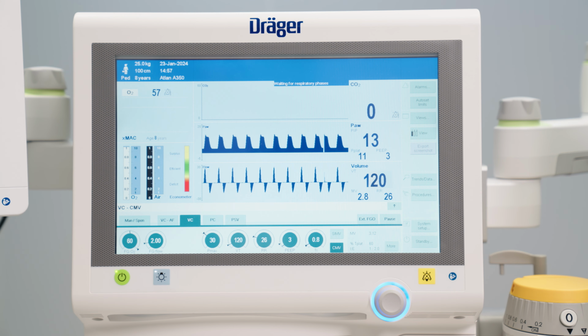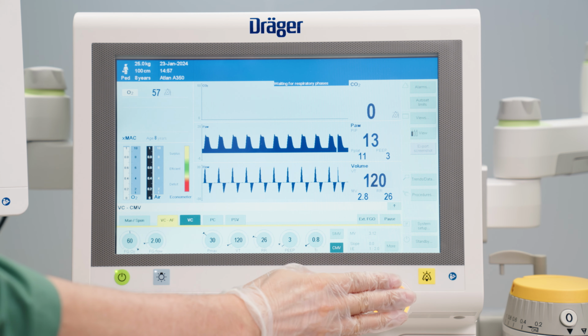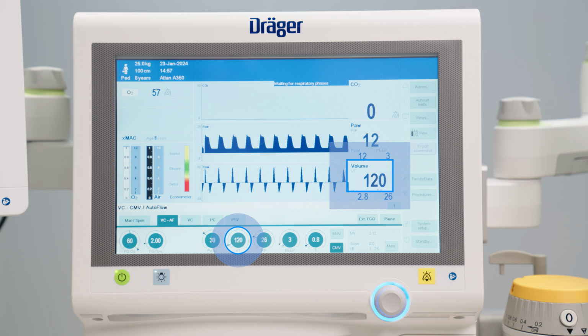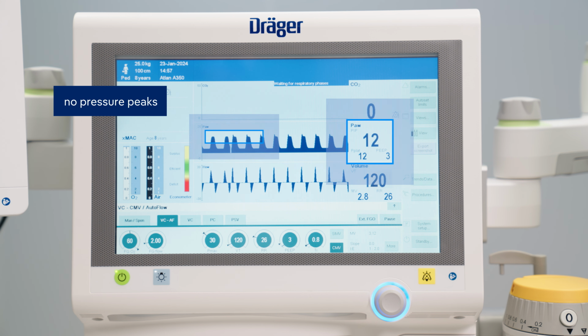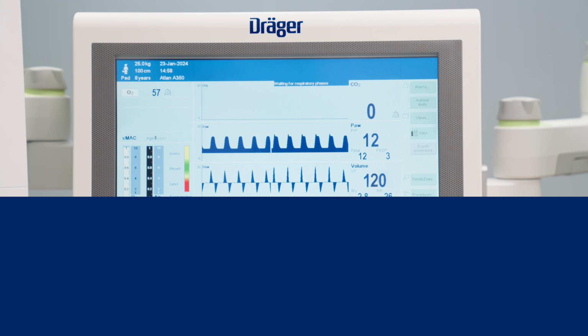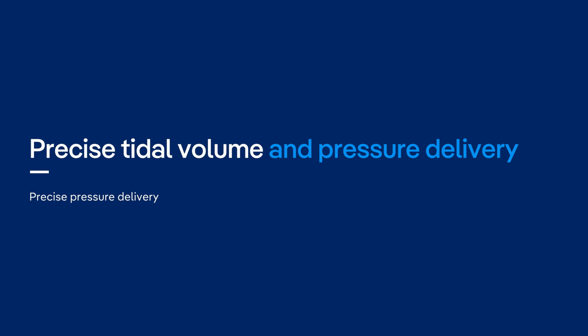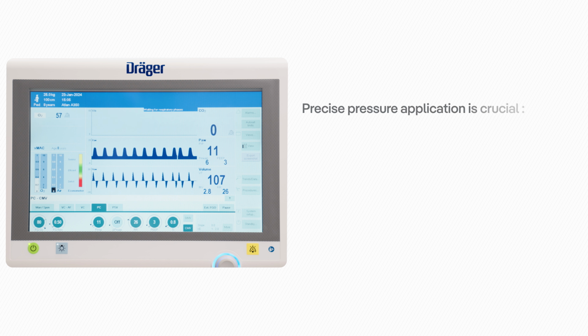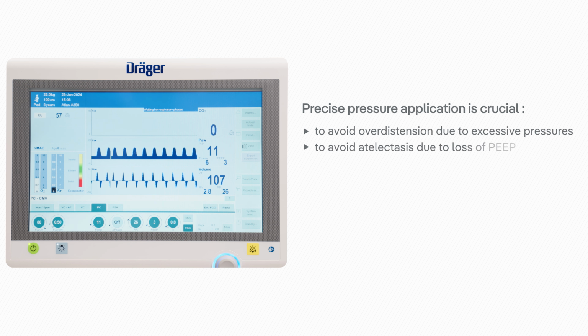The volume control autoflow mode of Dräger ventilators combines the advantages of volume-controlled and pressure-controlled ventilation. Autoflow ensures the delivery of the set tidal volume at the lowest possible pressure in a pressure-controlled pattern. Especially to protect the pediatric patient's lungs, precise application of ventilation pressures is of vital importance, because excessive pressures may harm the lung by overdistension, whereas loss of PEEP can induce atelectasis.